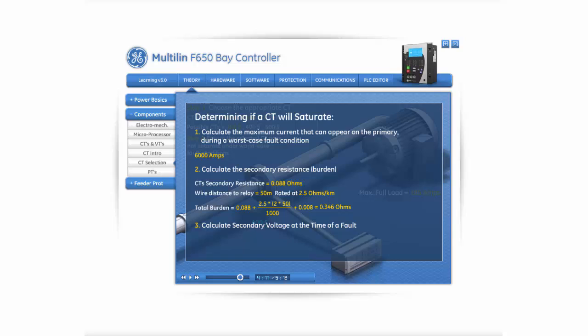Now the secondary voltage at the time of a worst-case fault can be calculated. First, the total burden resistance, 0.346 ohms, is multiplied by the maximum fault current, 6,000 amps. The result is then divided by the CT ratio, 300 to 5. Concluding that the secondary voltage at the time of a worst-case fault is 34.6 volts.